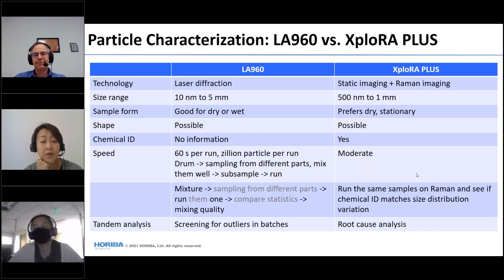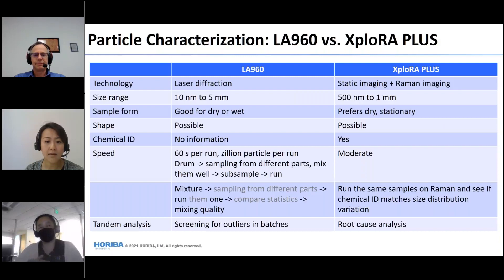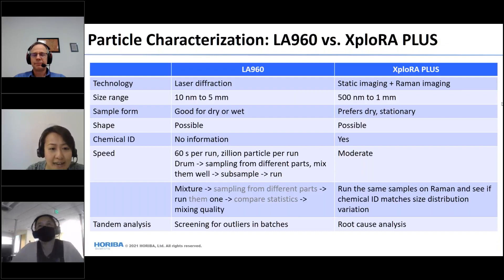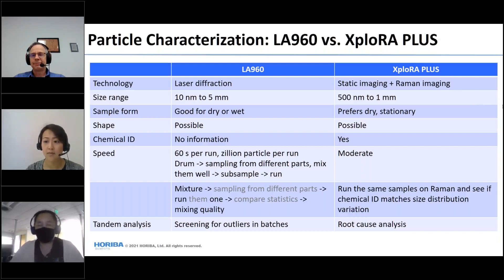Can the Raman mapping of particle chemical identity be implemented on an older Horiba Raman microscope with a software update? Yes, definitely. As long as you have the mapping stage, it is just an add-on to the software. Does the software for Xplora Plus contain image-based PSD — particle size distribution — analysis? Yes. It is based on optical microscope image or Raman image, and you can get size distribution based on diameter equivalent, area equivalent diameter, or area itself.